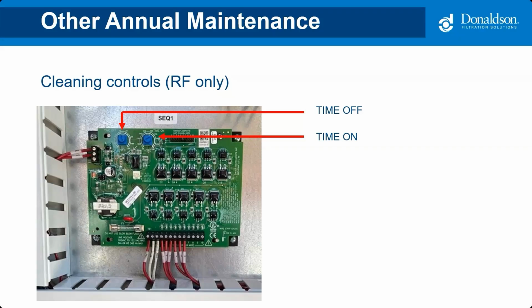If it's turned the opposite way and you're not cleaning often enough, well, now you run the risk of the opposite problem, where you're overloading filters too much in between pulsing, and you could either shorten your filter life, or you get into a situation where the filters just aren't pulsing off now because they've depth loaded faster than they should have. So this is a good check that I recommend you do once a year.